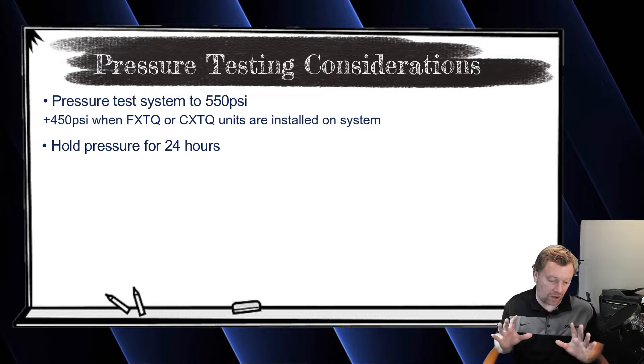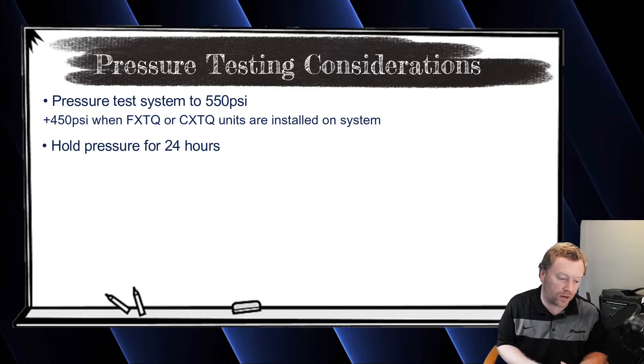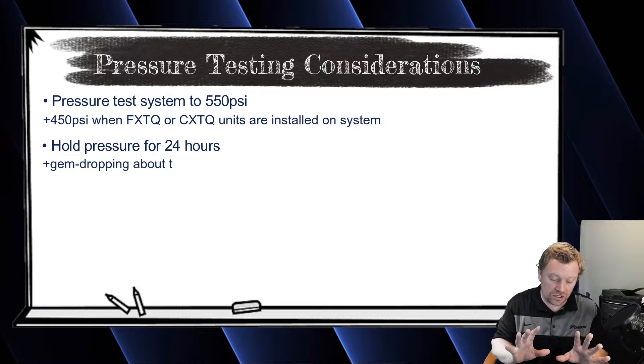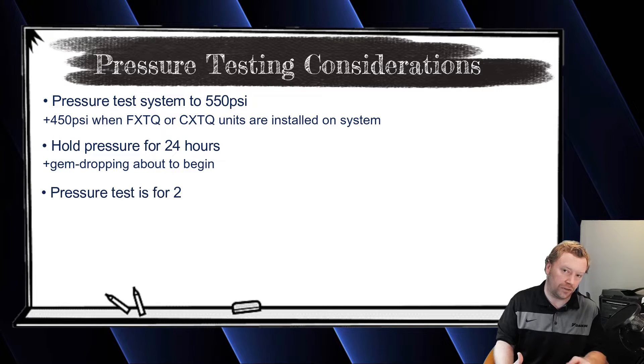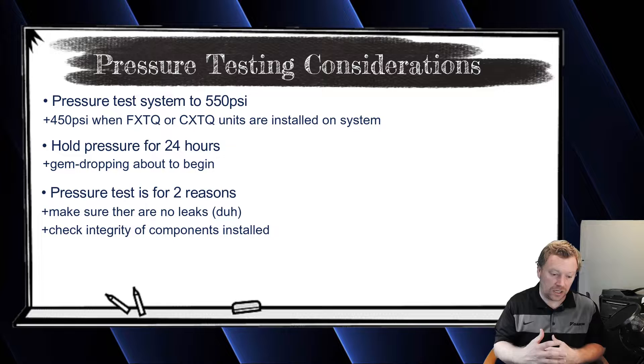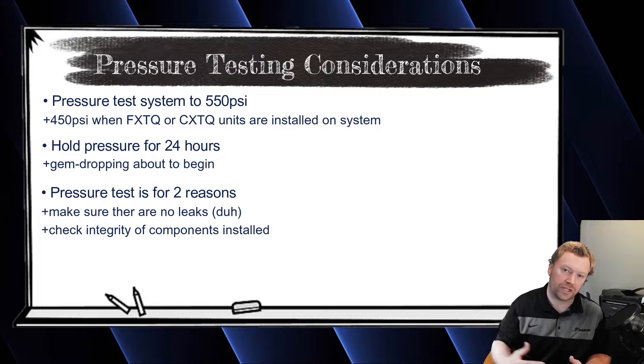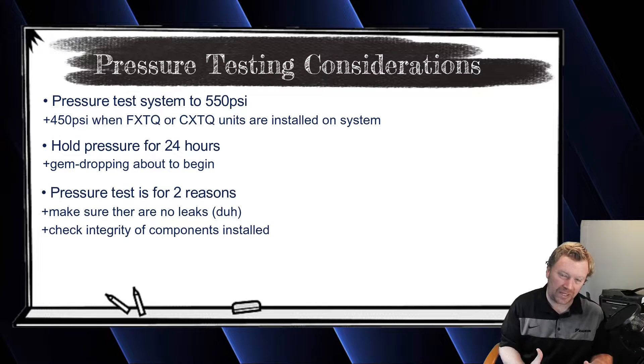So 550 PSI for how long? 24 hours. Now I get a lot of pushback on that. If you can't do a full 24-hour pressure test, you need to do a pressure test for as long as you can. We aren't just looking for leaks here — we're also looking for component integrity. I can't tell you how many times I've had a line set fracture just on the roll — a bad line set from the factory — where the leak appeared two, three, or four hours into the pressure test.